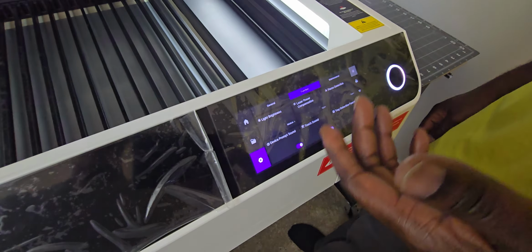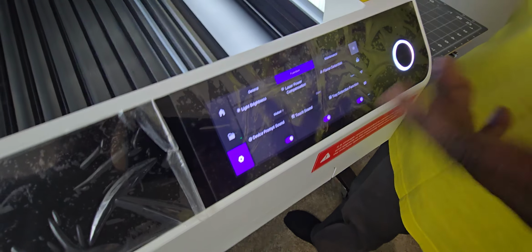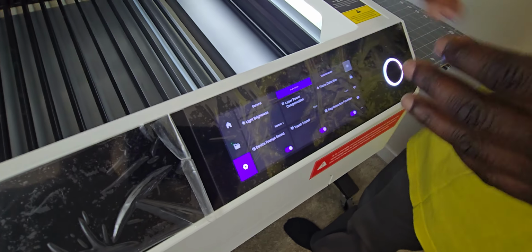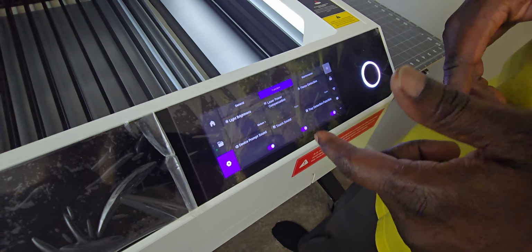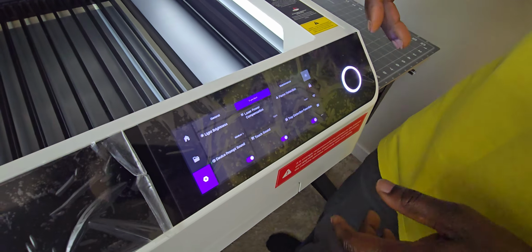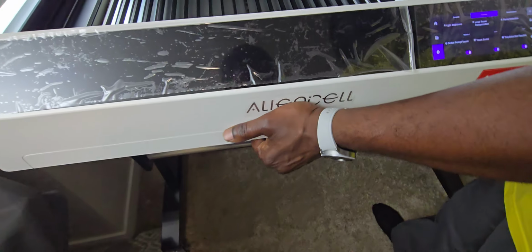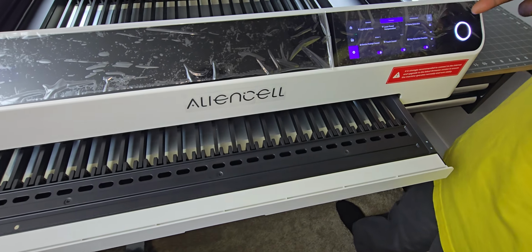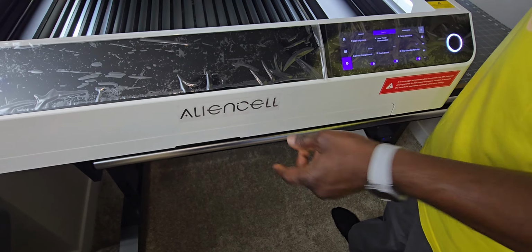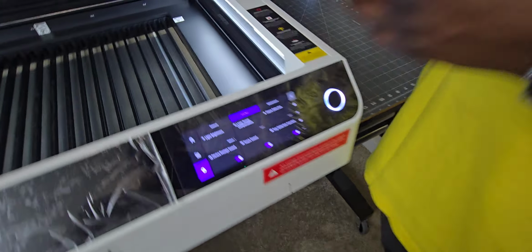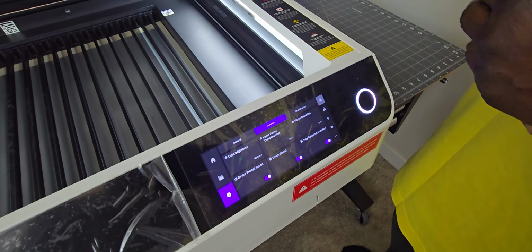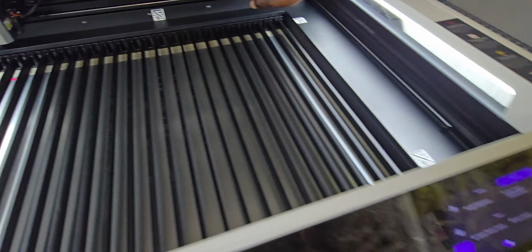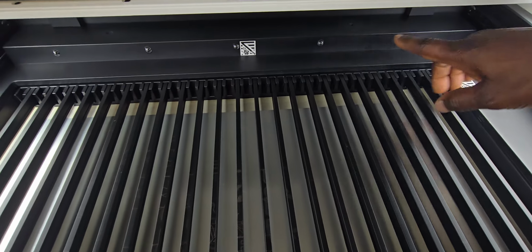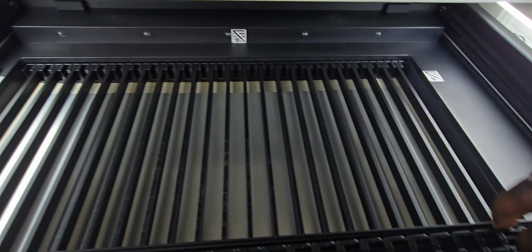Here you have your device prompt sound, which is whenever you press the buttons, you hear that noise. You have your touch screen and also your tray detection. When you pull the tray out, the machine beeps, and when you push it back in, the machine beeps, so that detects that the tray is in there. Also you have your flame detection, and as you can see in the back right here, there are 5 flame detection sensors back there, and then they have 4 more right up in front here along the way.